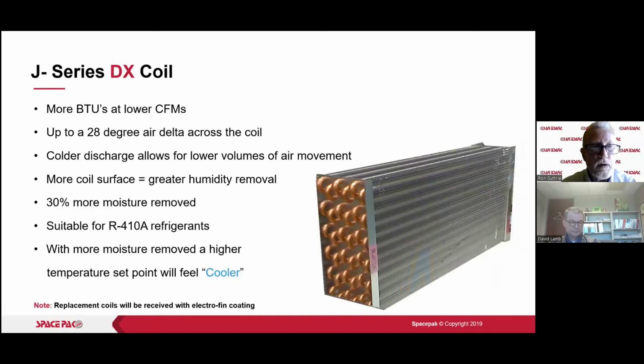All right, so we've got a 6-row coil. We're typically between 25 and 28 degree temperature difference across the coil. That colder discharge allows for lower volumes of air movement. So we have less CFM, but we have cooler air, and we have that moving at a high velocity through the system. That's how we get those BTUs to where we want those BTUs. We've got more coil surface because we have those 6 rows, so we have greater humidity removal. And this also goes back to picking the unit that gives you the most BTUs and not necessarily the highest nominal SEER rating.